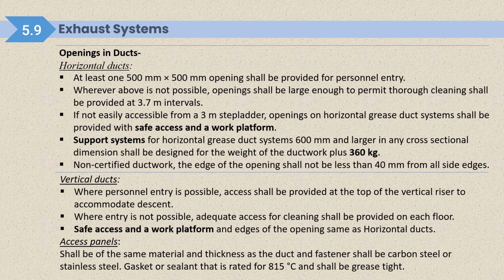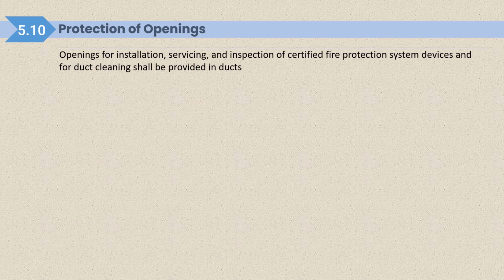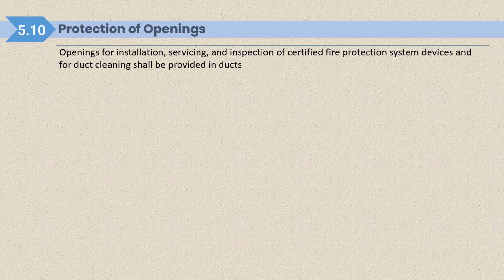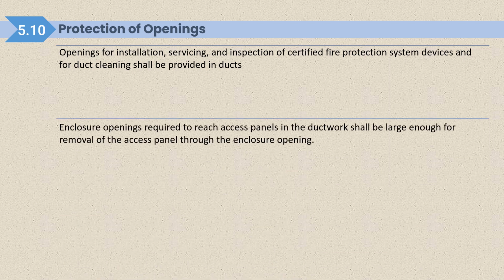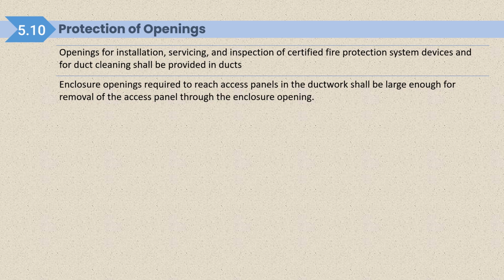Access panel shall be of the same material and thickness as the duct, and fasteners shall be carbon steel or stainless steel. So we have to use fasteners of carbon steel or stainless steel only. Gasket or sealant shall be rated for 815 degrees centigrade and shall be grease tight. Protection of openings for installation, servicing and inspection of certified fire protection system devices and for duct cleaning shall be provided in duct enclosures. Openings required to reach the access panel in the ductwork shall be large enough for removal of the access panel through the enclosure opening.